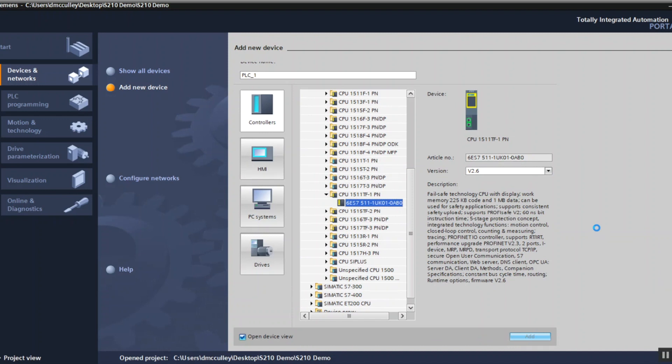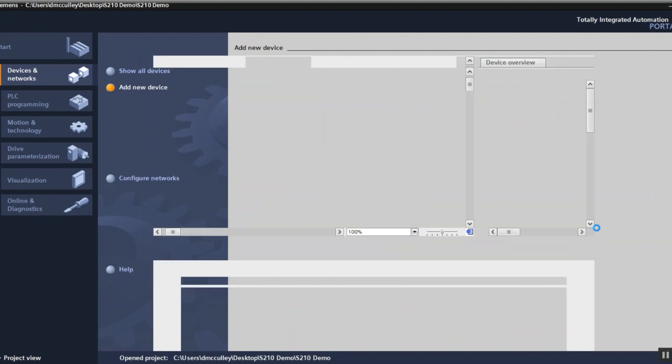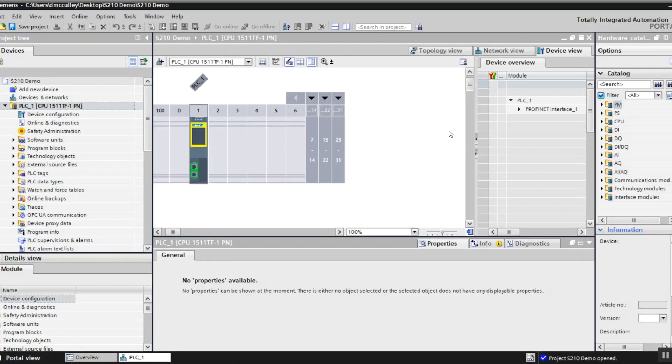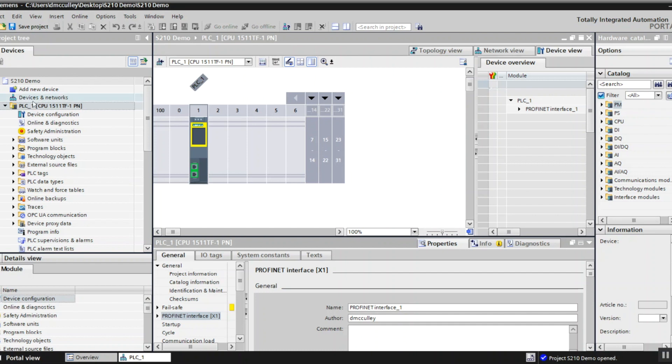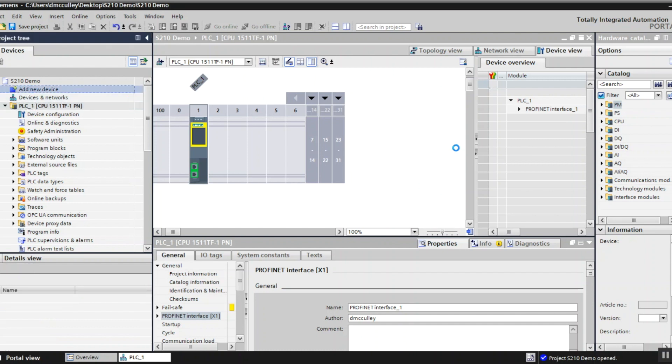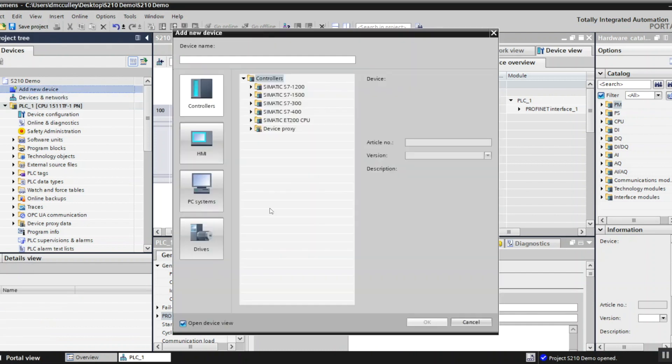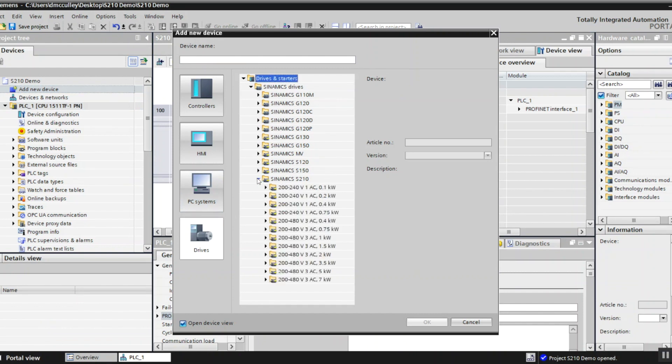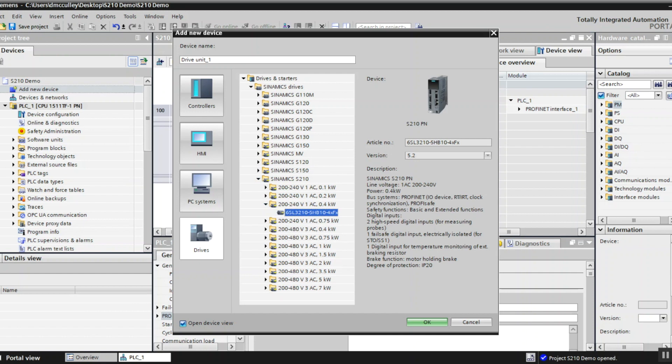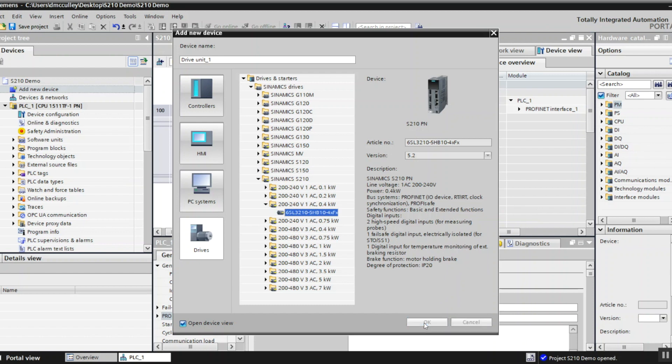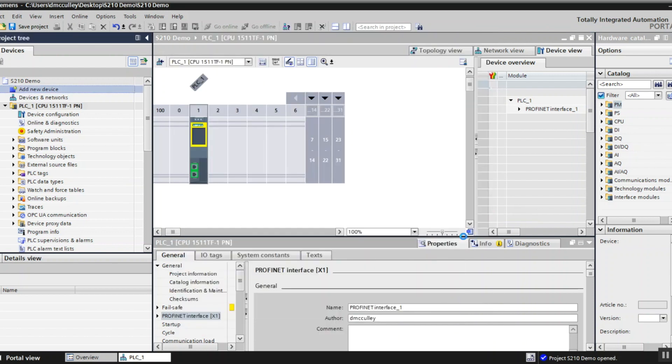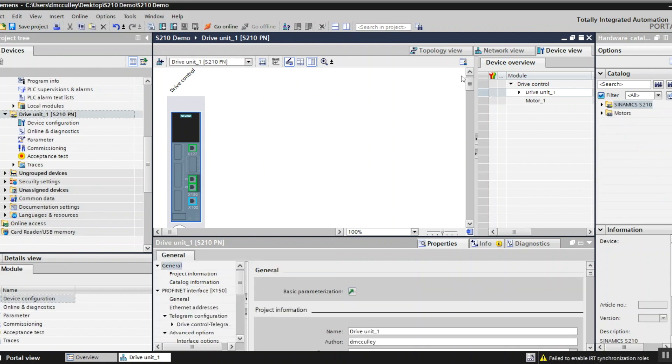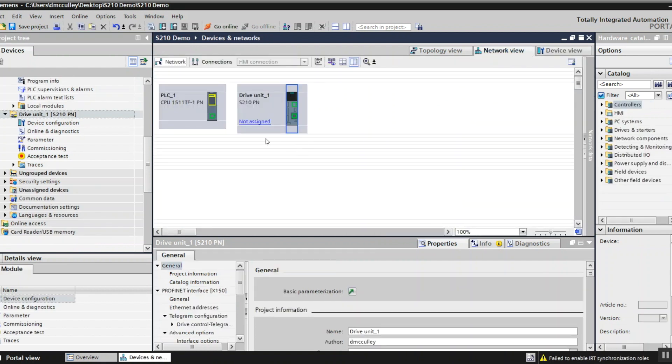Add that. Next I'm going to add my drive. Over here I'll click on add new device, choose drives S210 0.4 kW firmware version 5.2, which is the minimum you can have to have the S210 in the TIA Portal Start Drive. Then I want to go to my network view and click not assigned.